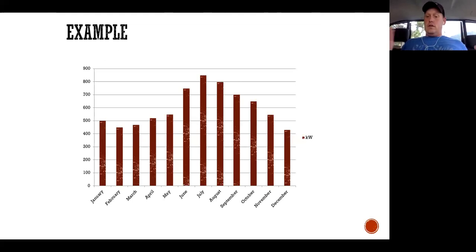Okay, why are you operating your utility use during June, July, and August? They didn't need to. They had their outside air dampers open, letting hot Houston air into the building during peak time, and then they'd have to wring that humidity out of the air by bringing cooling on and bringing it down to 32 degrees. A common fix is to move the dehumidification process from peak times to early in the morning and close those outside air dampers, since there's nobody in the room and they didn't need them open. That was a no-cost fix.